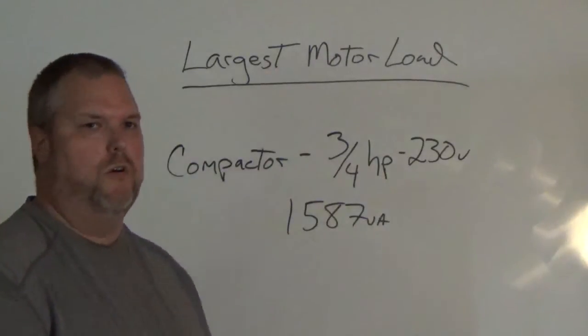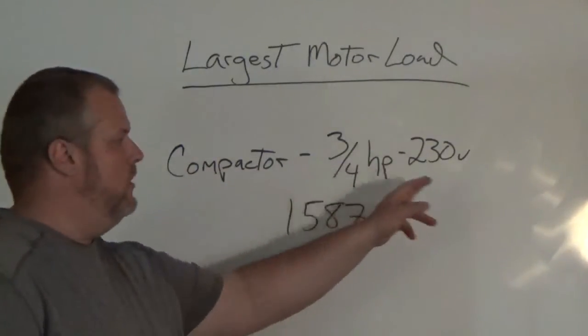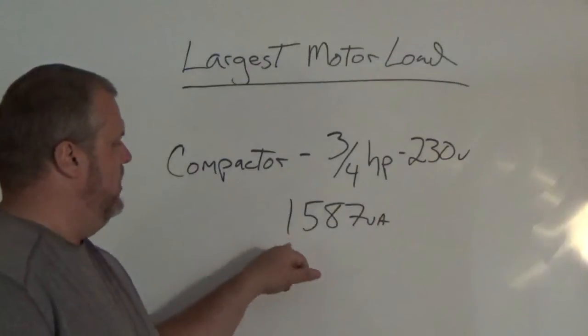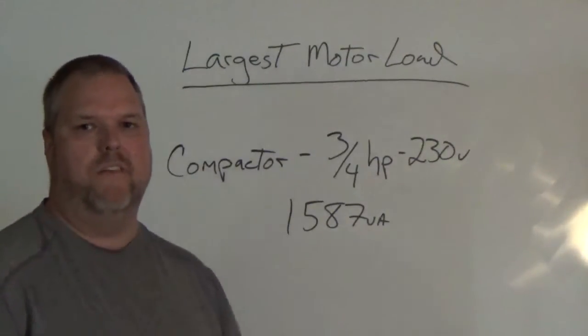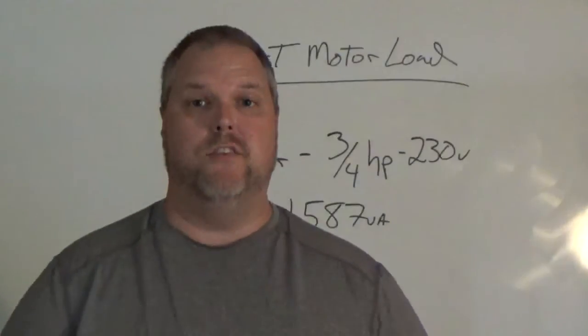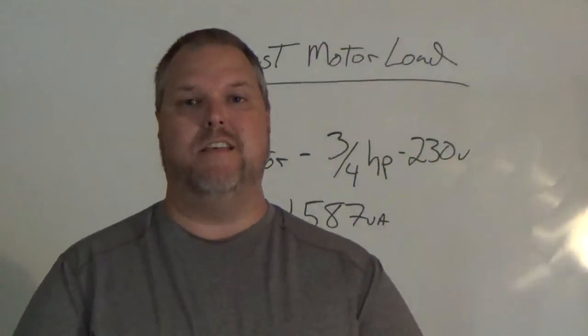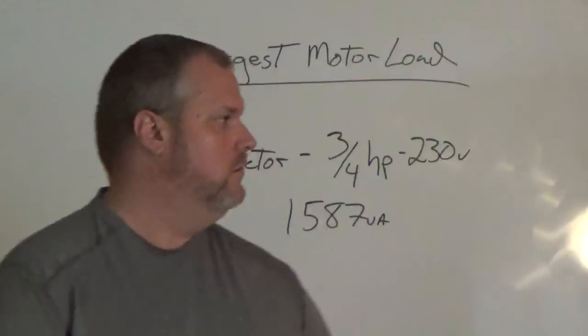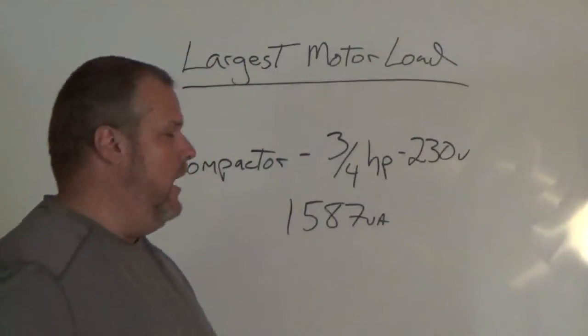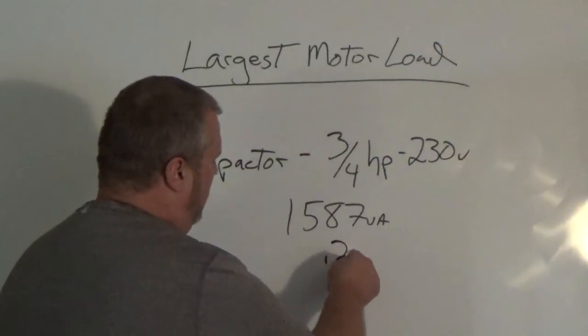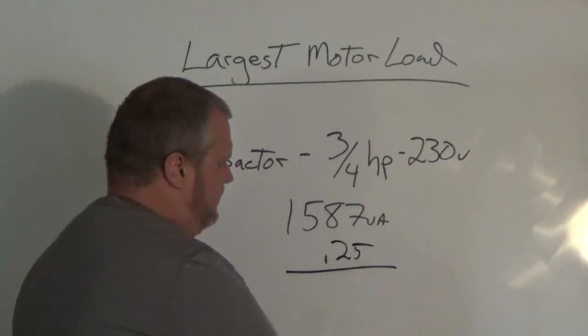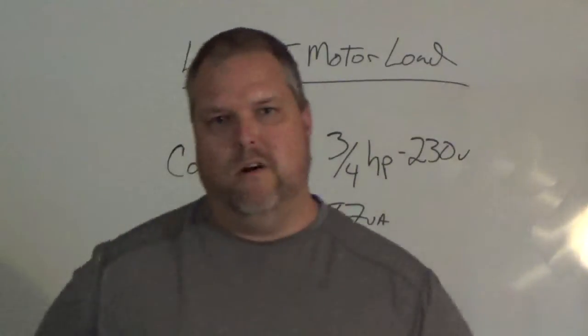In our fixed appliances, our compactor was our largest motor. It was a three-quarter horsepower at 230 volts, which gives us 1587 VA. What we have to do now is take our largest load, the compactor load, and multiply it by 0.25.